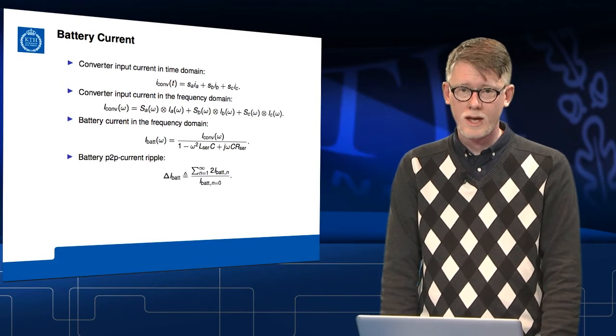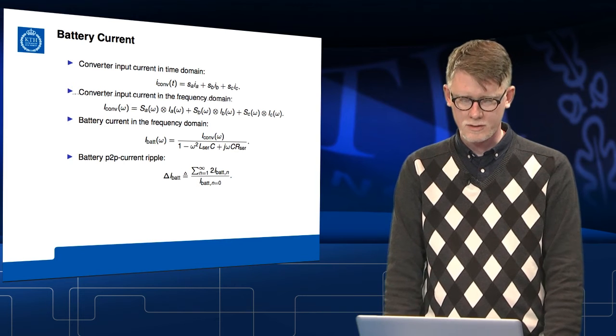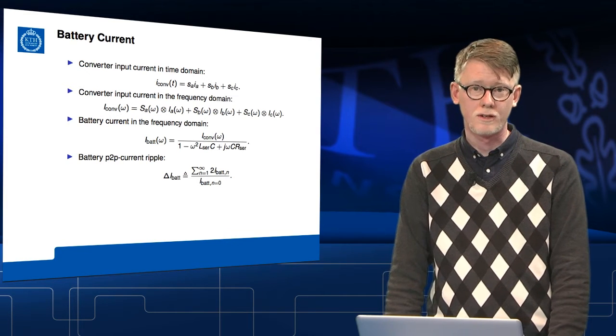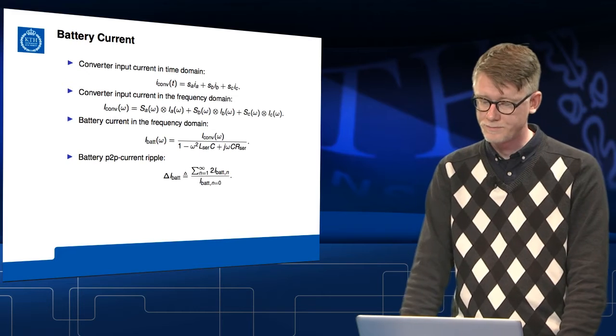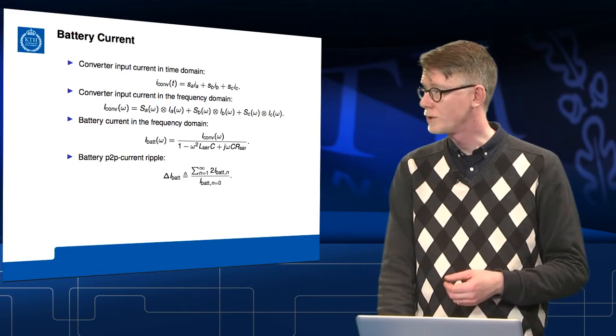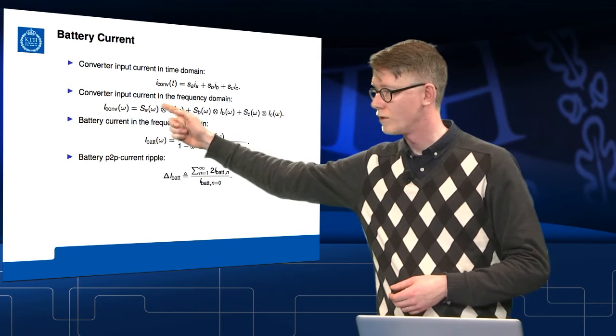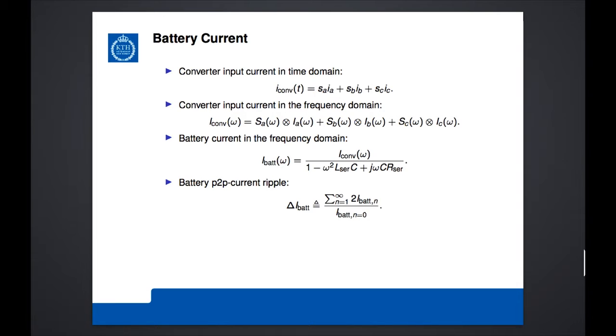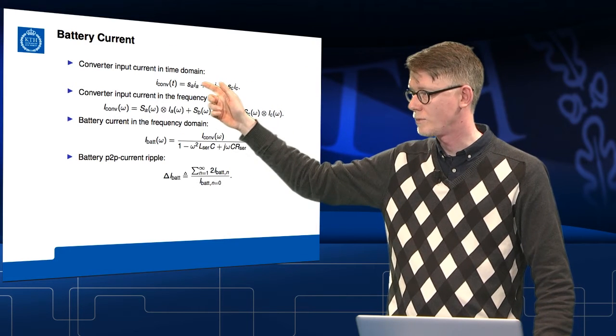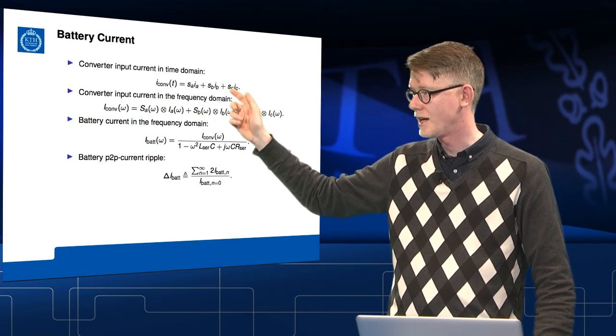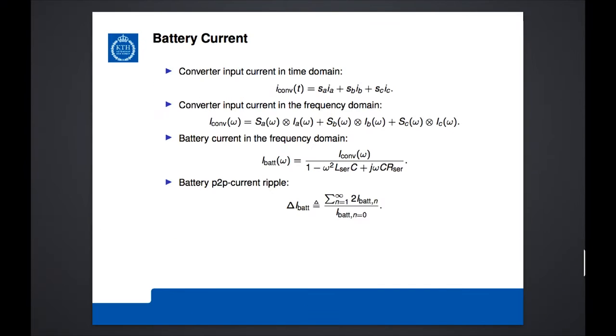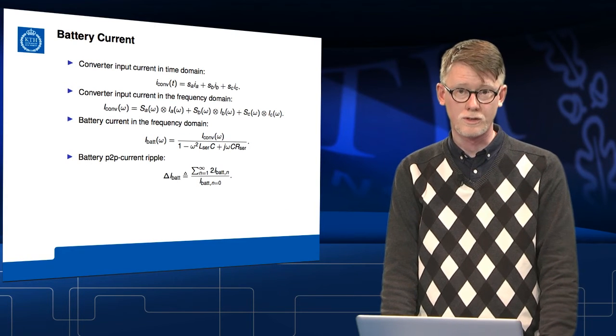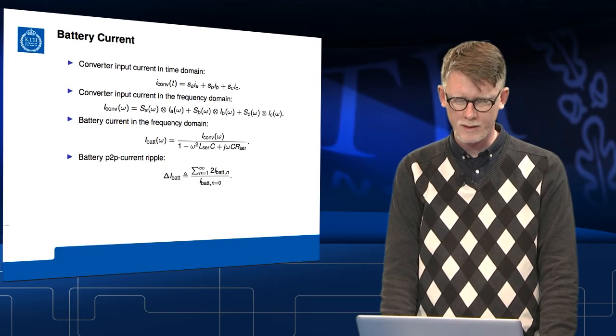One of the main functions of the DC-link capacitor is to limit the battery current ripple within acceptable levels. The converter input current, I-conv, can be expressed as a sum of the 3-phase currents multiplied with switching functions SA, SB and SC, which equal 1 if the upper transistor is turned on, or 0 if the corresponding lower transistor is turned on.